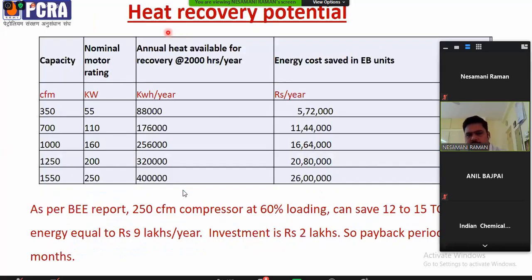So what is the heat recovery potential? From the kilowatts, we can say that almost 60% of the power can be recovered in the form of heat. One sample calculation I have put up for easy understanding: for example, if it is a 110 kilowatt compressor, we can have a heat of 1.7 lakh kilowatt hours per annum. It will give a reduction in cost of almost 11 lakhs.